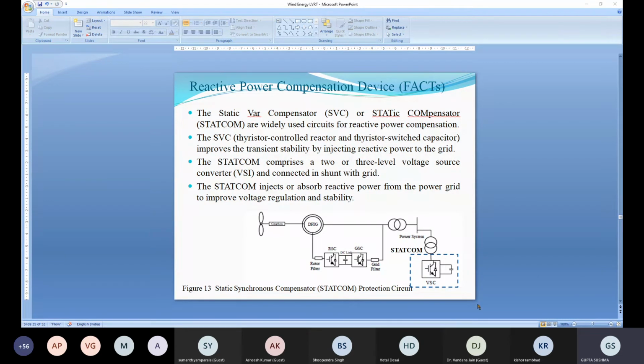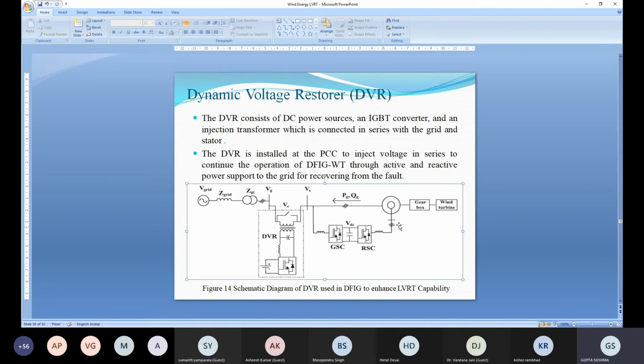And next is the DVR. You know this circuit also. DVR is connected in series with the grid. StatCom is connected in shunt and DVR is connected in series. It consists of a VSI and an injection transformer, and when there is a disturbance in the grid, it provides reactive power, and under normal operation it takes active power and maintains the DC link voltage over here. So these are connected at the grid side, not the converter side. So these are the reactive power compensation circuits.